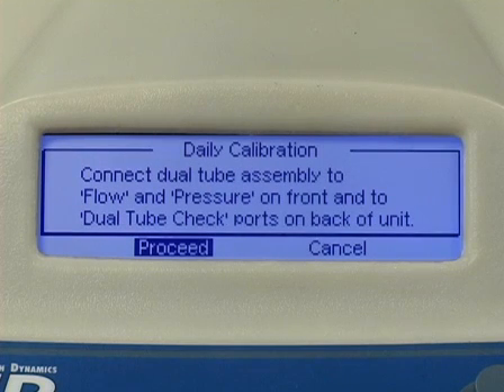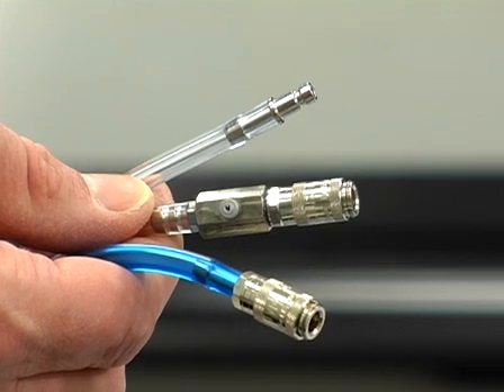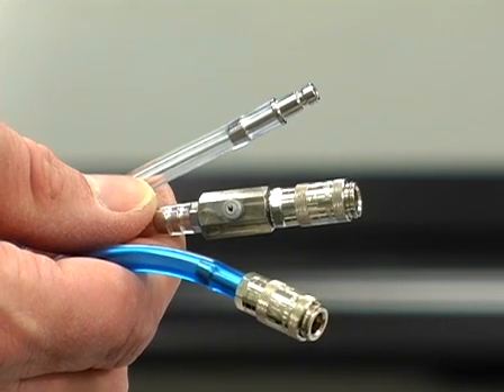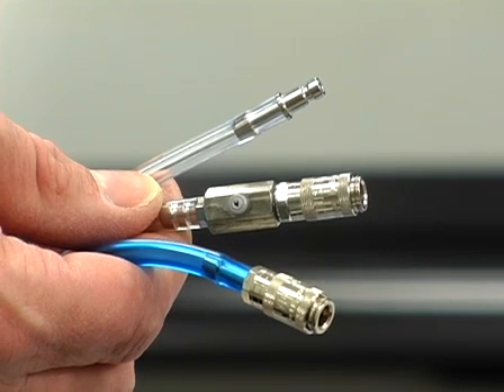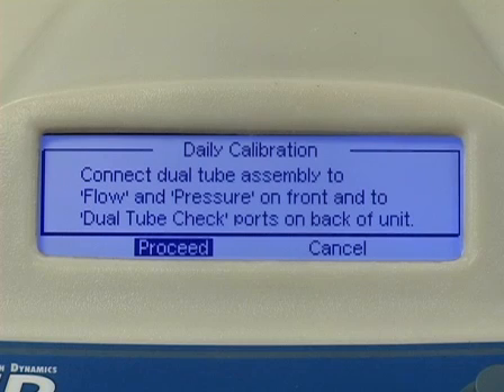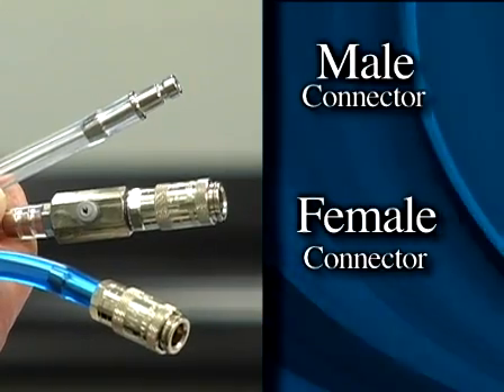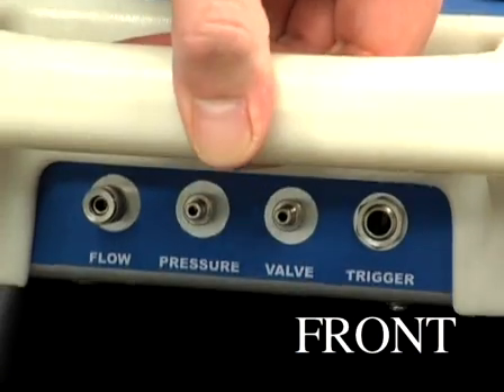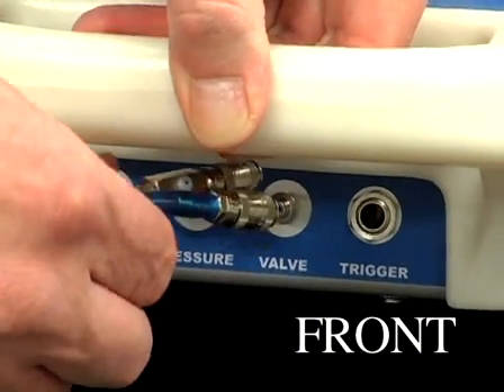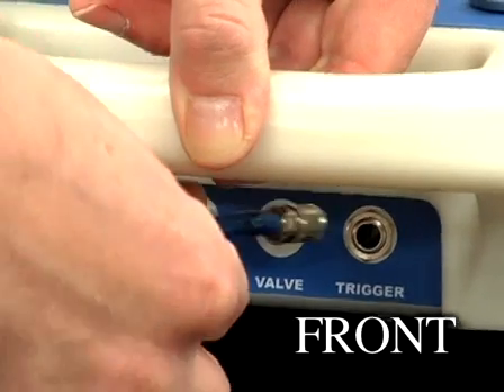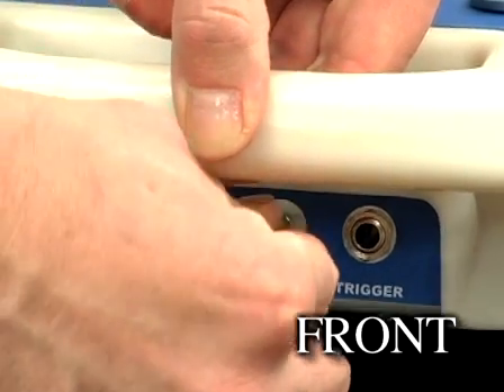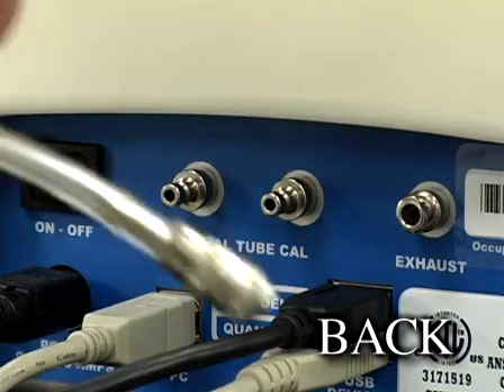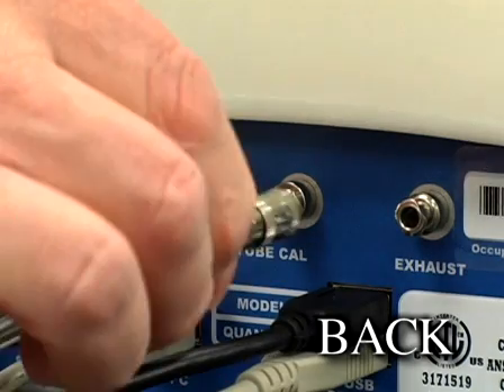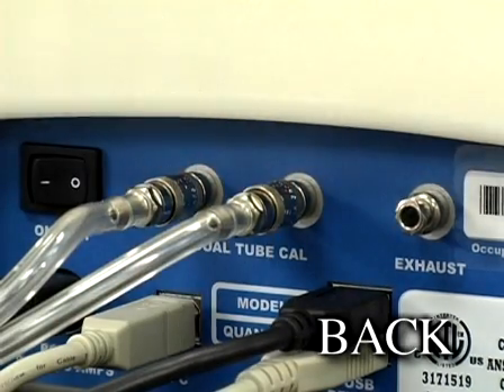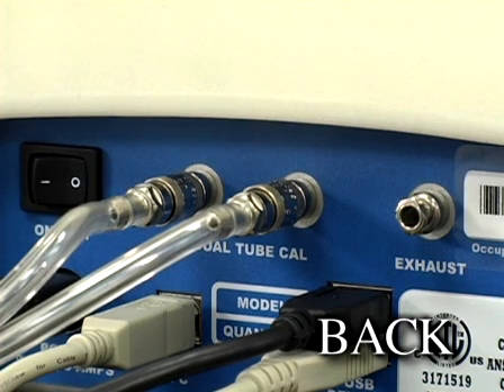Once the unit is zeroed, the next step will be a dual tube calibration. You'll notice there are 2 clear tubes and 1 blue tube. The 2 clear tubes are a part of the triple tube assembly, and these are referred to as the dual tubes. The screen will prompt you to connect the dual tubes to the front and back of the Quantifit. One end of the dual tube has a male and female connection. These will be connected to the flow and pressure connections on the front of the unit. Although not necessary for the calibration, you may want to connect the blue tube to the valve port at this time. Connect the opposite ends of the clear tubes to the dual tube cal ports on the back of the instrument. It does not matter which port you connect them to since they are interchangeable.